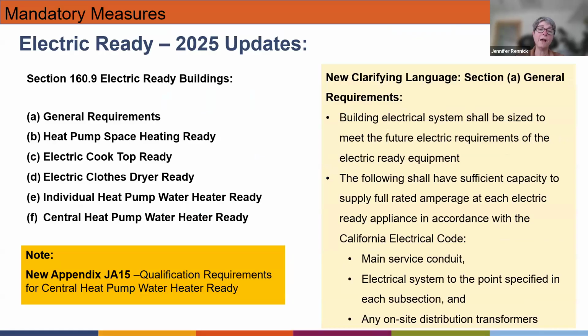Under the 2025 code, the electric ready building section, they've pulled that requirement. They pulled that specifically having to do with the hot water into the electric ready section, 160.9. So when you get the new code, those parts aren't going to be with the hot water anymore. It's going to be with the electric ready section of the code. And along with this, there's a new appendix, JA15. And it specifically talks about the qualification requirements for a central heat pump water heater. And that section is new.